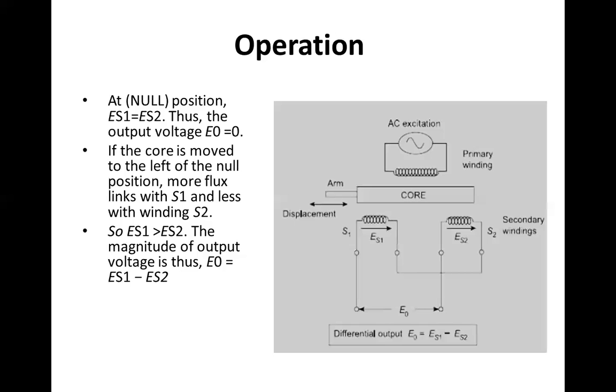Now let's come to the operation of this LVDT. At null position, ES1 is equal to ES2. Thus, the output voltage E0 is equal to 0. If the core is moved to the left of the null position, more flux links with S1 and less flux will link with S2. So ES1 will be greater than ES2. The magnitude of output voltage is thus E0 equals ES1 minus ES2.